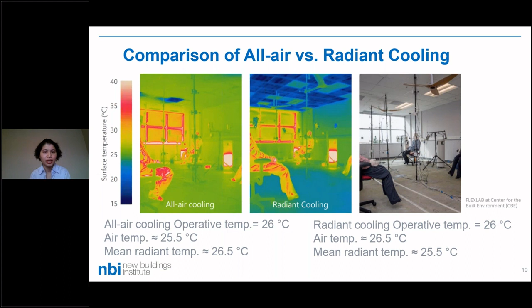From an energy perspective, radiant heating cooling systems are about 20 to 60% more energy efficient compared to all-air systems, depending on the type and climate zone being compared, as shown in the graph on the right. These systems are also very common in high-performing buildings—NBI's net zero energy buildings database shows over 42% of net zero energy buildings use radiant heating cooling, so these systems absolutely allow buildings to meet net zero energy targets.